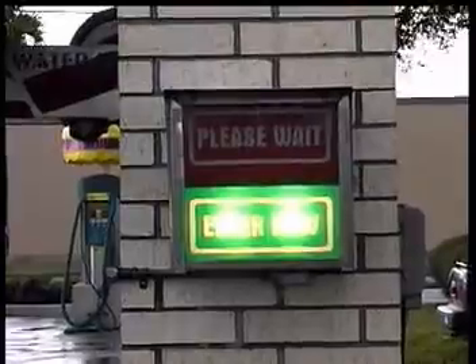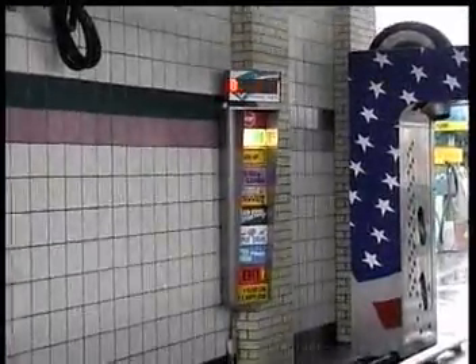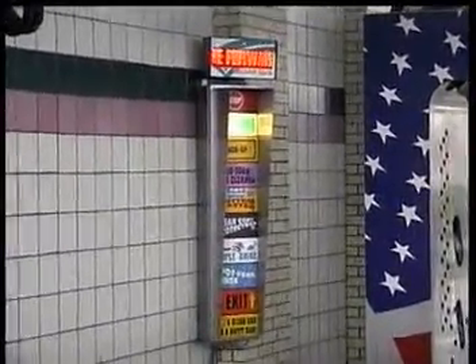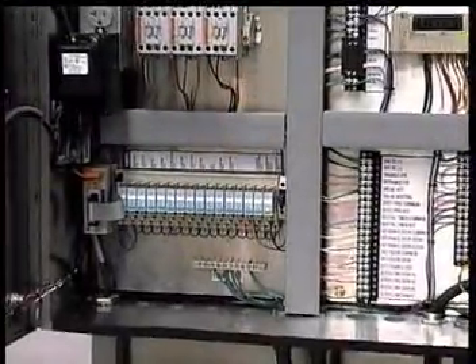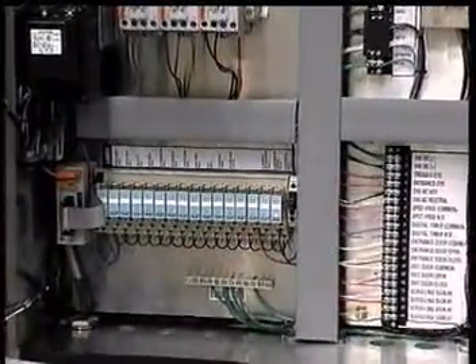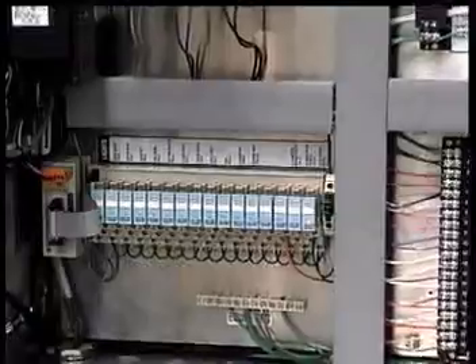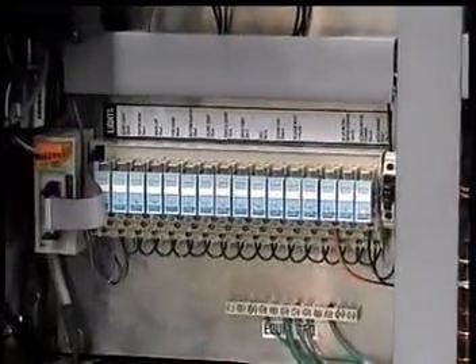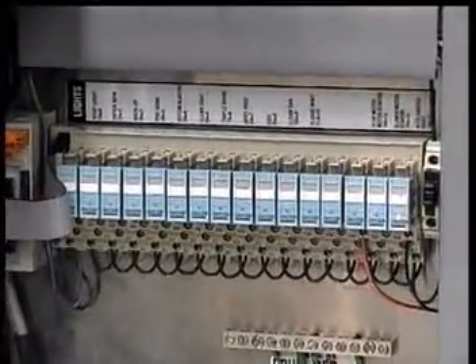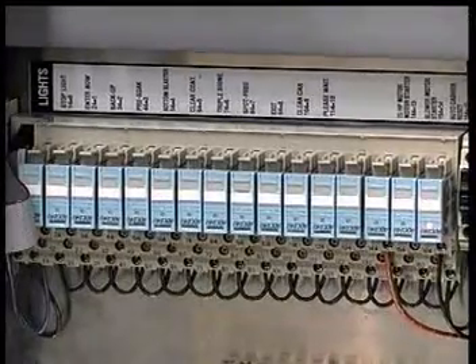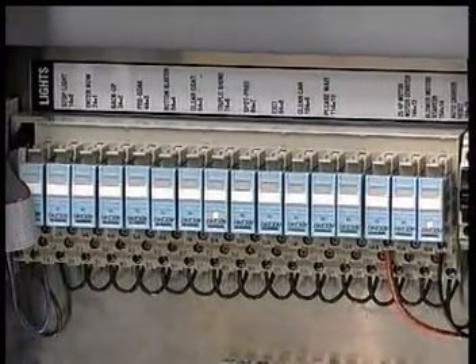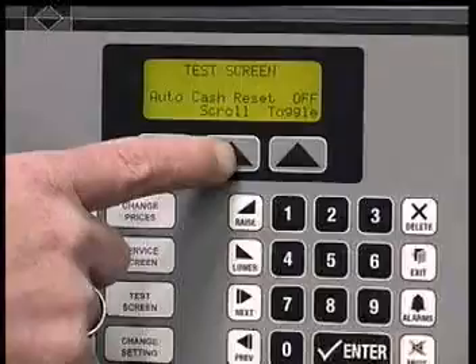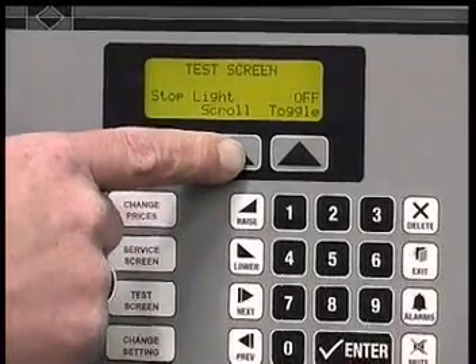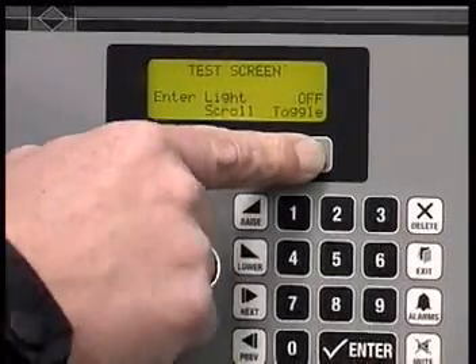The entrance sign and the in-bay instructional sign are powered by 110 voltage. Located in the bottom left-hand side of the control panel is the ZOC16 relay card that controls these signs. When called for, the processor sends a 110 volt signal to the top side of the corresponding relay, energizing the relay which activates the bay sign. They can also be activated manually through the test screen on the interface panel.